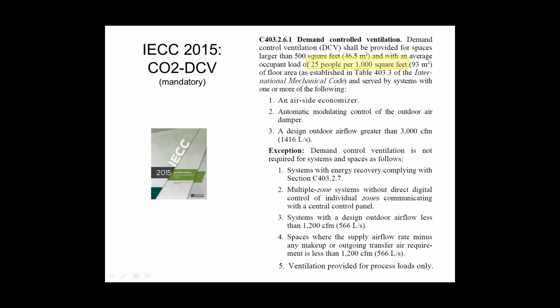Dale asks, is the design OA based on IMC, or will the Chicago OA requirements also work as the go or no-go for DCV? The code that you would have to follow, Dale, would be whatever code is in the jurisdiction that you're in. So if you're in the city of Chicago, you've got to follow the Chicago ventilation code. If you are in one of the suburbs, you're following probably the IMC and some specific version of the IMC. I will explain both of those codes here in a minute for everybody else, but whatever ventilation code you're following will dictate how much outside air you need. And then once you know how much outside air you're required to bring in by code, then you can look over here at exception number 3 on the screen and see if that applies to you or doesn't apply to you for the CO2 sensor.